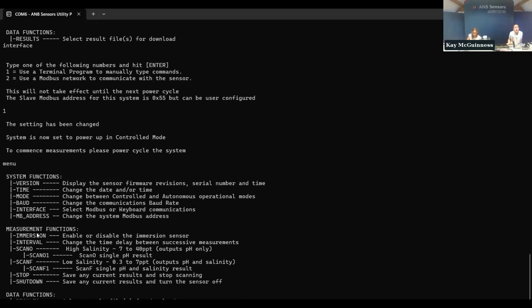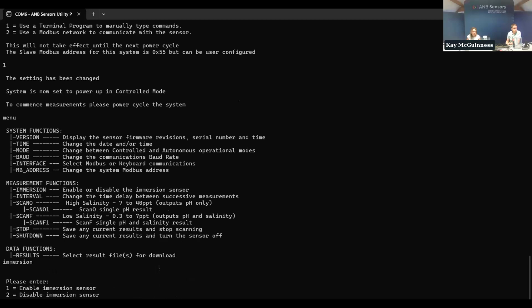Perfect. Okay, so we move on to the measurement functions. If you type immersion, it allows you to enable or disable the immersion sensor. So all the sensors now have an immersion sensor on them. So they'll only start scanning once the transducer surface is wet. This is really handy when you first get your sensor. The immersion sensor will be on, but if you want to test the comms on the bench without putting it into any water, you can turn the immersion sensor off and check the comms.